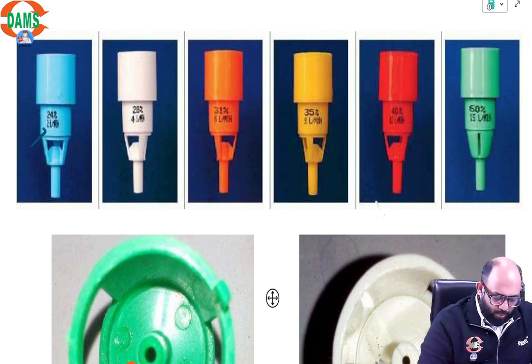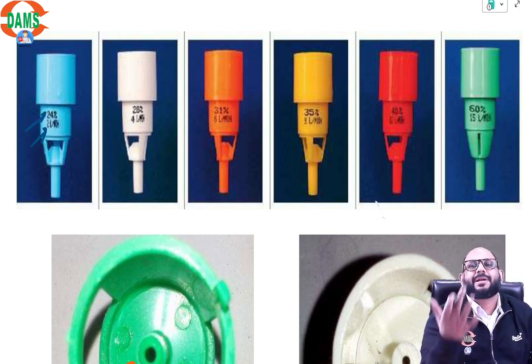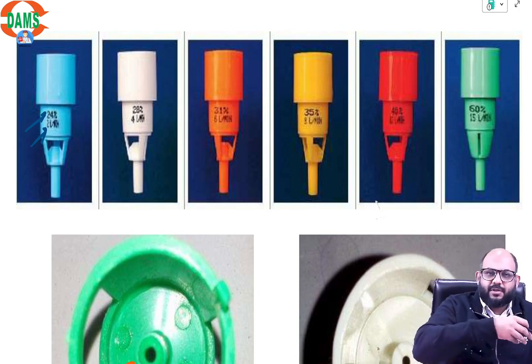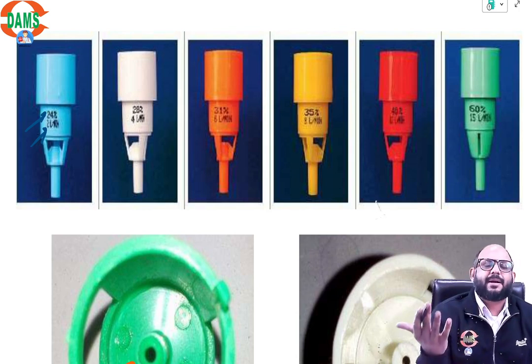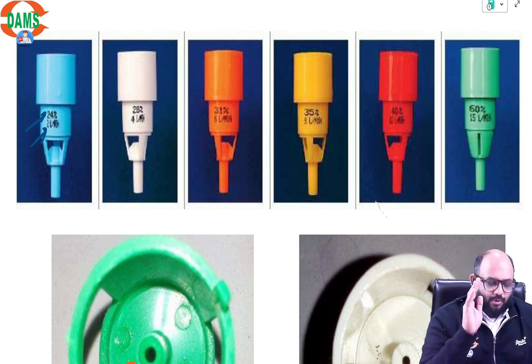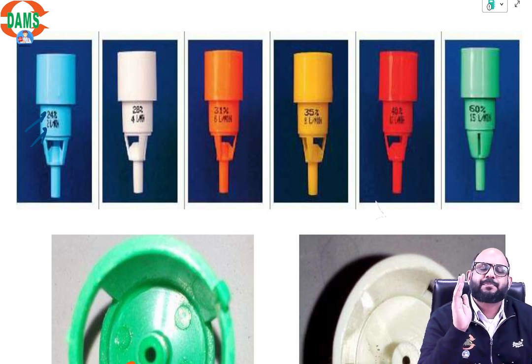So here it is written 2 liters per minute oxygen will give 24%. Now what will happen? Even if the patient is breathing very fast, the patient will take in more gases. Now with 2 liters of oxygen, if the flow increases, again more entrainment, more oxygen will come, more air will come, and again it will be 24. If the patient is breathing less, then less velocity, less oxygen will come, again it will be 24. So at 2 liters per minute, irrespective of the patient's respiratory pattern, the FiO2 delivered would be 24. That is why it is called a fixed performance device.